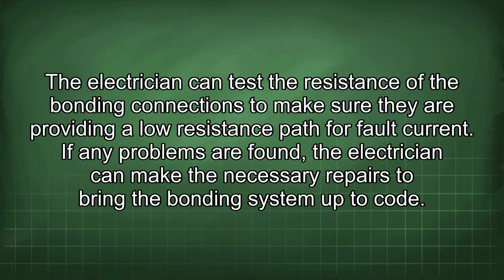The electrician can test the resistance of the bonding connections to make sure they are providing a low resistance path for fault current. If any problems are found, the electrician can make the necessary repairs to bring the bonding system up to code.